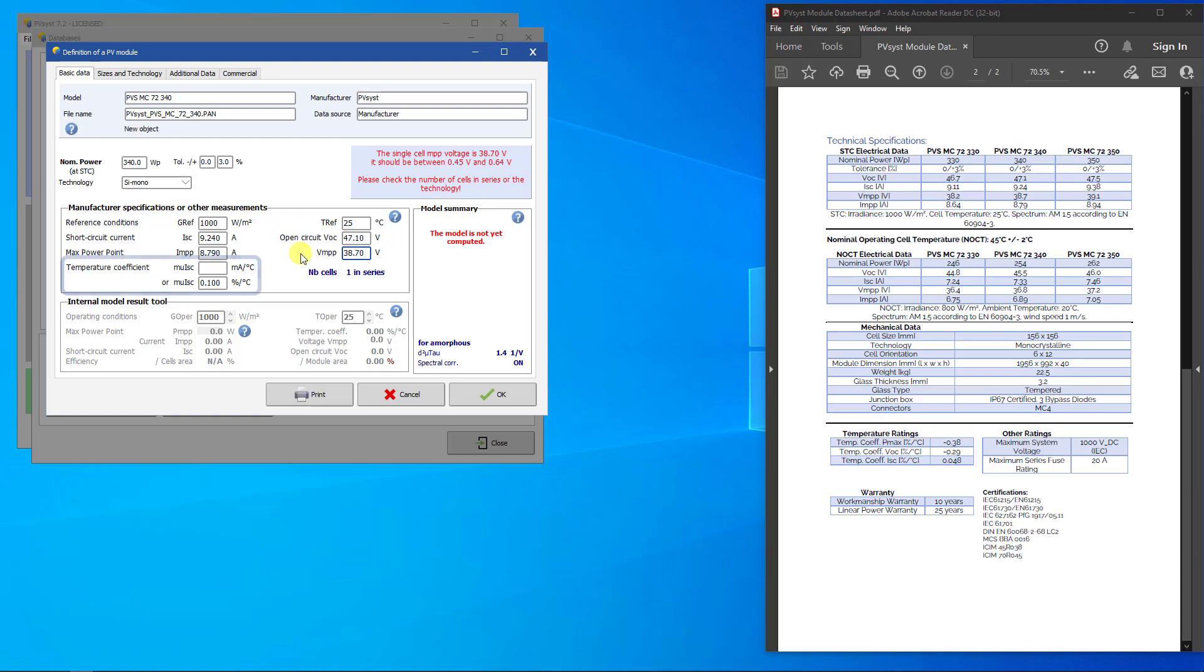Next, we will input the temperature coefficient. In PVSyst, we use the ISC temperature coefficient, which is sometimes referred to as alpha. PVSyst can either use the value in milliamps per degree Celsius or percent per degree Celsius. In our datasheet, the value is given in percent per degree Celsius.